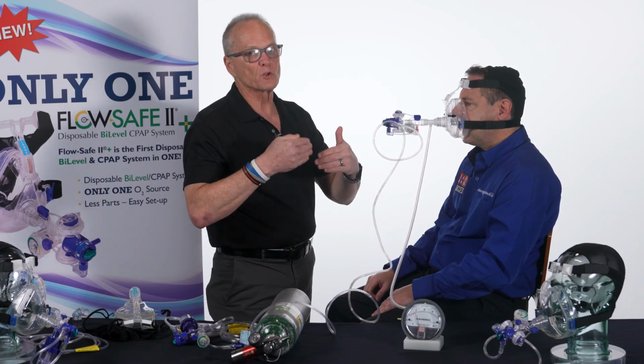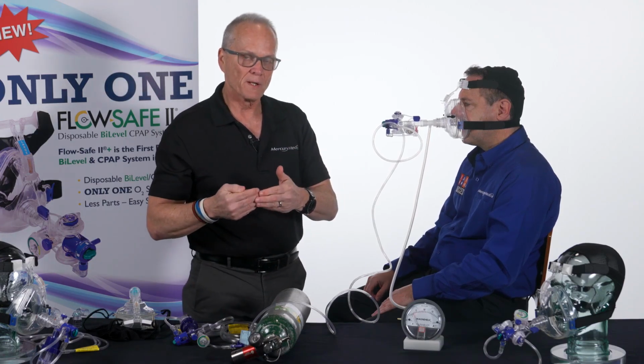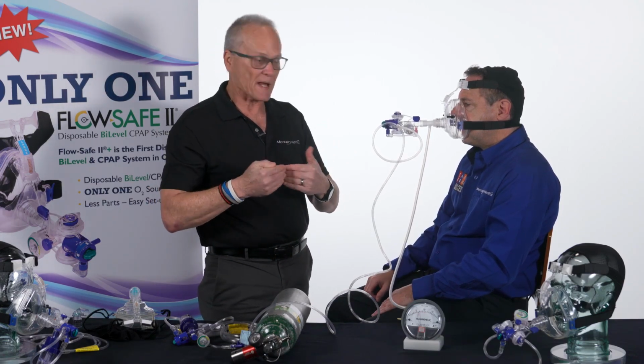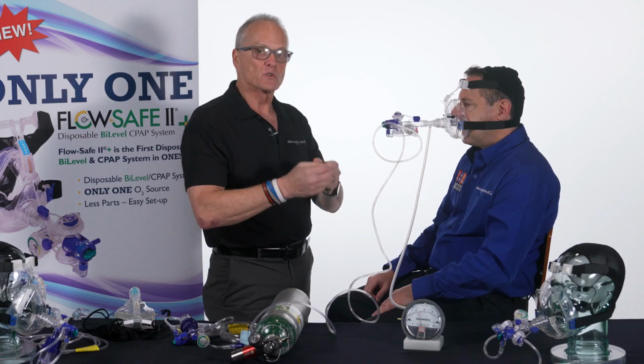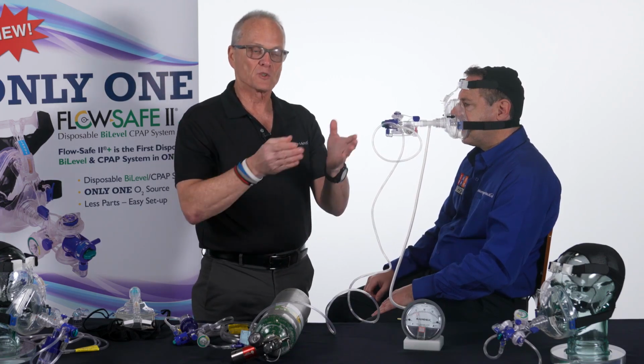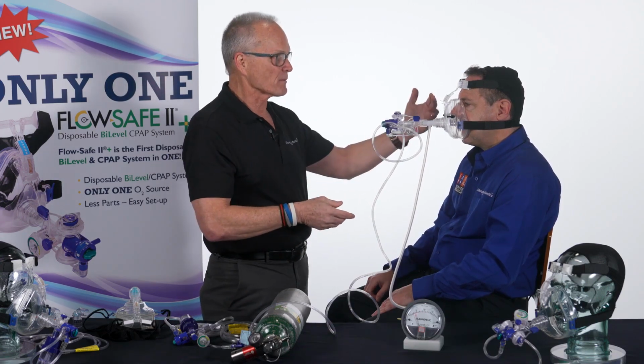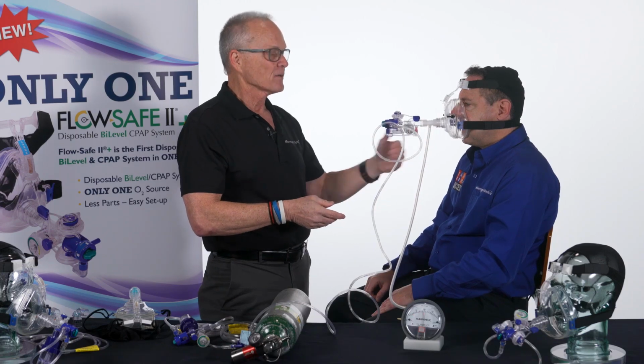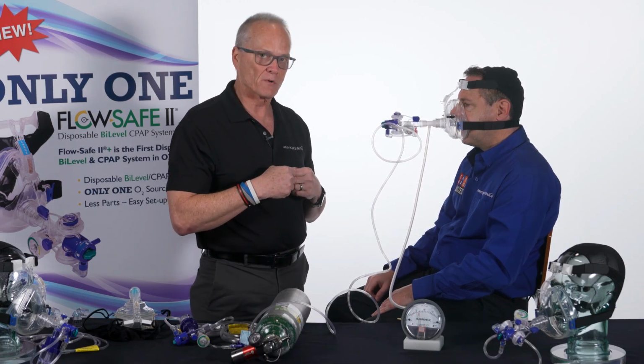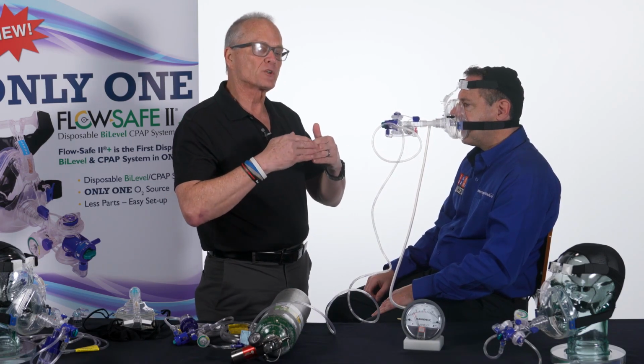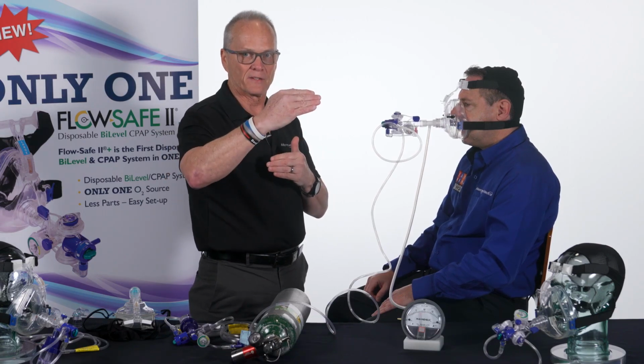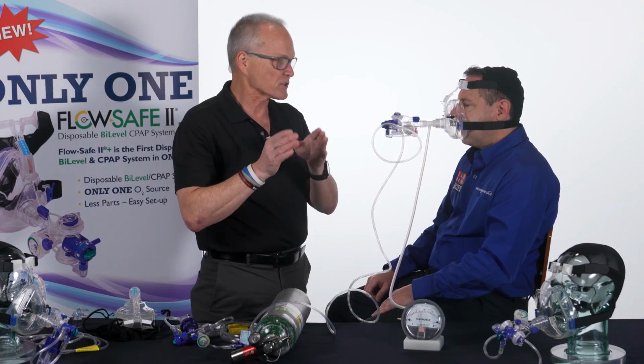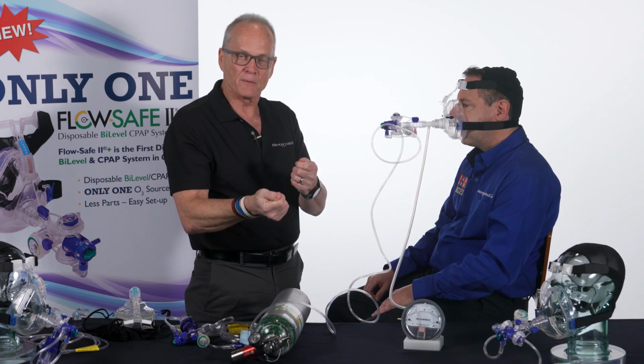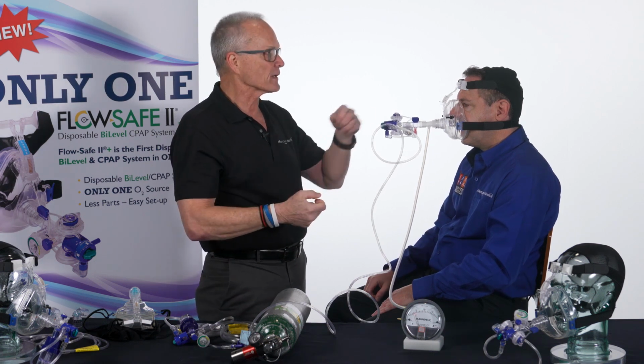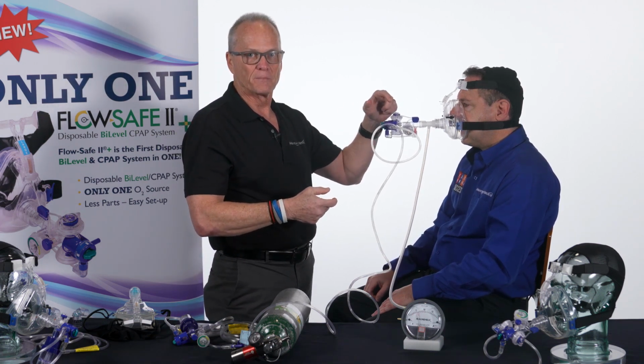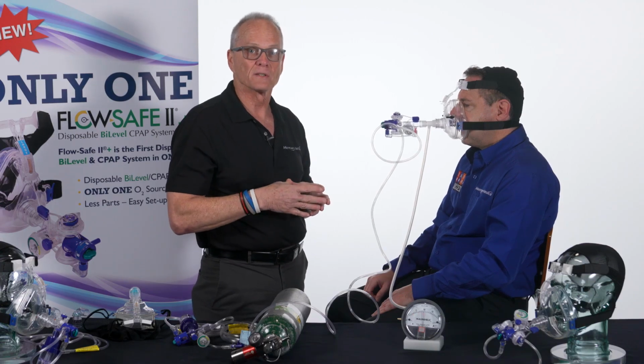To use FlowSafe 2 Plus, it's very important that we follow those steps as I outlined there. Start in CPAP. Start it at 5. Make sure your mask is not leaking. Make sure he's not drawing it down to 0. Then adjust your CPAP up to 10. If everything still stays fine, it's still not leaking, then you can flip your switch to BiLevel and adjust your EPAP. And that's really all there is to it.